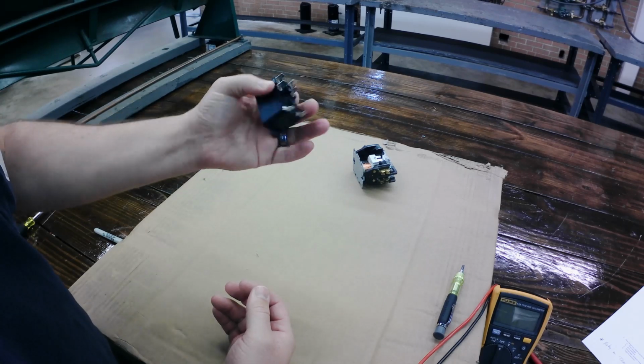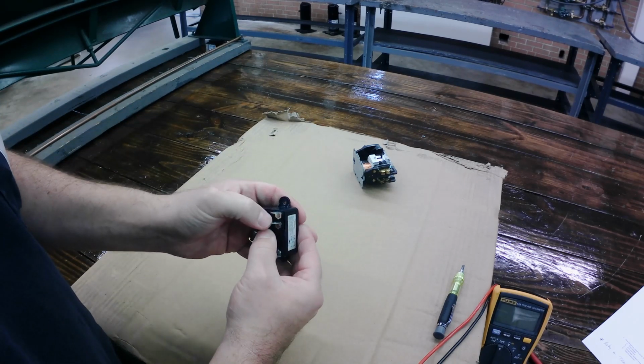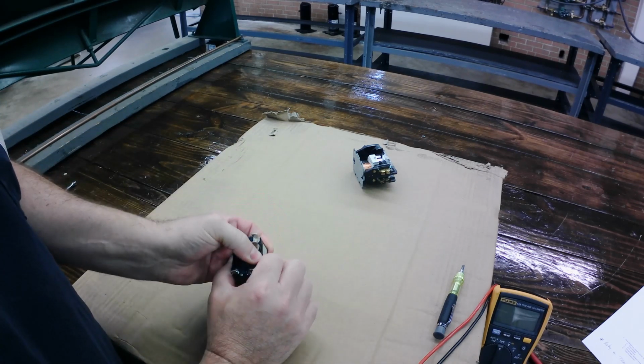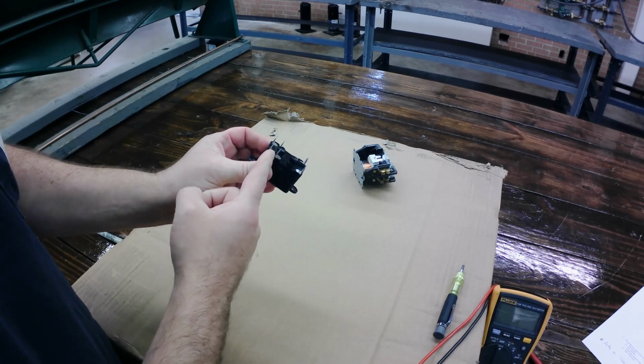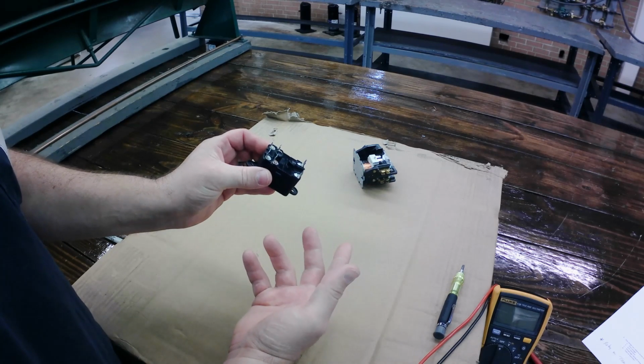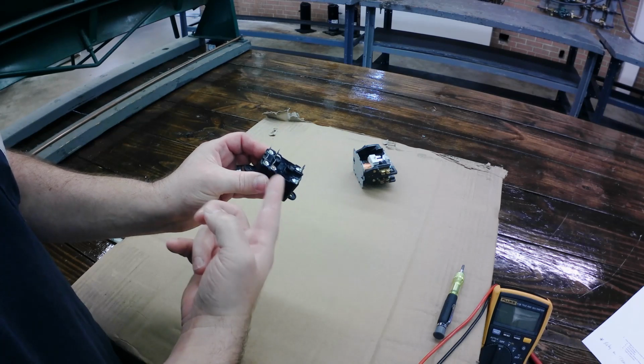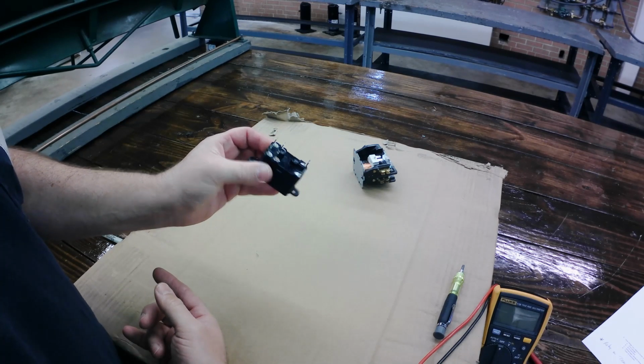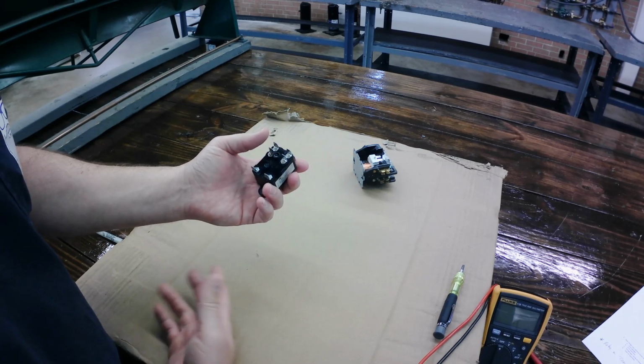The fan relay is going to be the same thing. Doesn't matter if the coil is shorted out or open, or if the switches are burned up or something. Either part goes bad, you replace the whole. All right, but you have to know how to troubleshoot this.